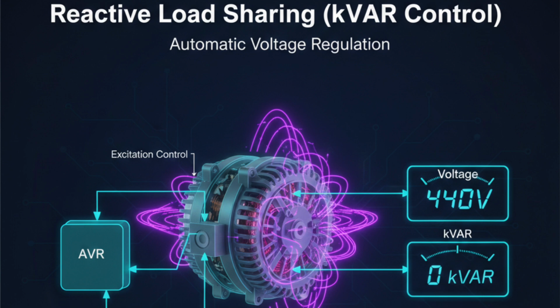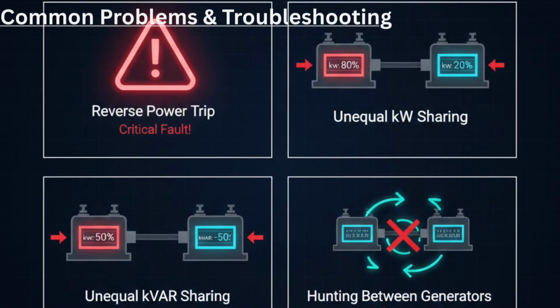Common problems or troubleshooting. Let us discuss some common problems during parallel operation. Reverse power trip. This happens when a generator starts consuming power instead of producing it. Unequal kW sharing. This may be caused by faulty governor or incorrect droop settings. Unequal kVAR sharing. Usually caused by AVR misadjustment. Hunting between generators. This is continuous fluctuation in load due to poor control tuning. To troubleshoot, check governor settings. Check AVR settings. Verify sensor feedback signals. Check protection relay parameters. Understanding the root cause prevents serious damage. Always monitor load meters carefully.